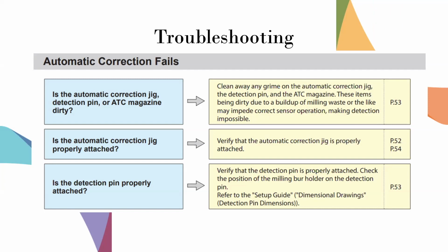I would imagine that since the calibration pin and the calibration jig probably spend most of their lives in a drawer under the machine or next to the machine, they're probably not getting all that dirty. You still want to wipe them down with isopropyl. Probably most of the problem happens in the jig holding fixture, the puck holder within the mill itself, because that is in the mill all the time. There's zirconia dust accumulating, and if that doesn't have a good electrical connection to the calibration jig, you could touch the calibration pin to the jig all you want, but we're not going to have that electrical continuity. Is that true in your experience, that it's usually the part of the mill where the puck holder gets loaded in that needs to be cleaned the best?